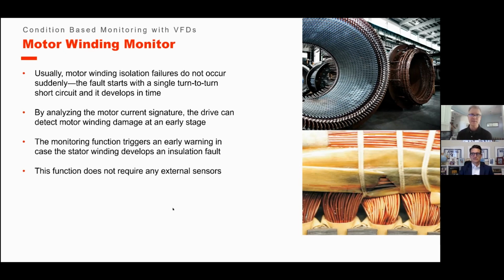They didn't have a lot of sensors or capabilities. If you had a ground fault, you literally physically blew the drive up. Today, that's not the case. If you have a ground fault, the drive just trips out. If you have a lot of faults, incoming, outgoing, the drive trips out. It saves itself from catastrophic damage. So you do not need any type of external sensor. You use the internal monitors, the internal sensors, and the internal algorithms in the processors to develop this technology.